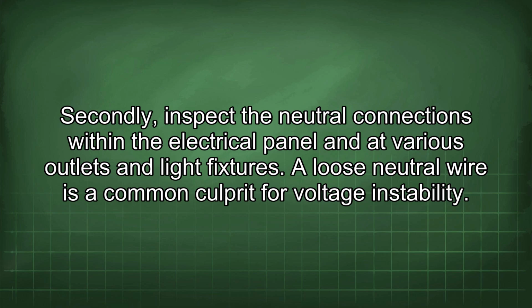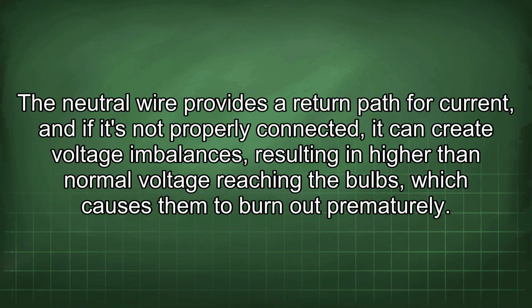Secondly, inspect the neutral connections within the electrical panel and at various outlets and light fixtures. A loose neutral wire is a common culprit for voltage instability. The neutral wire provides a return path for current, and if it's not properly connected, it can create voltage imbalances, resulting in higher than normal voltage reaching the bulbs, which causes them to burn out prematurely.